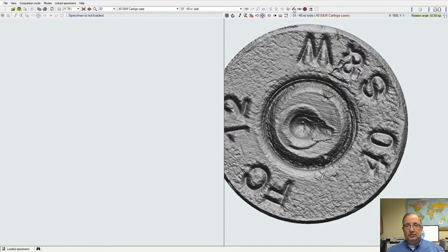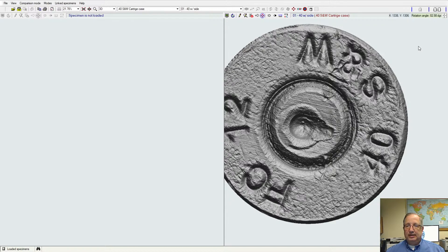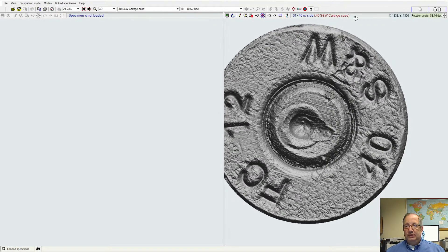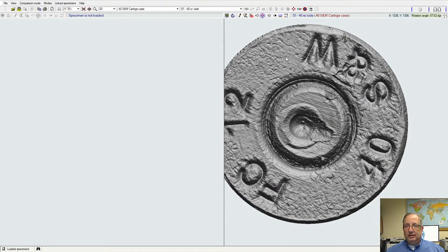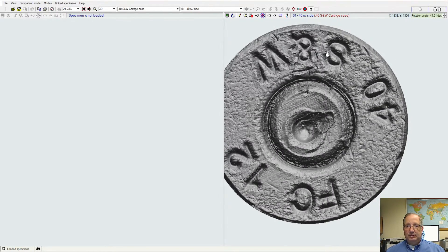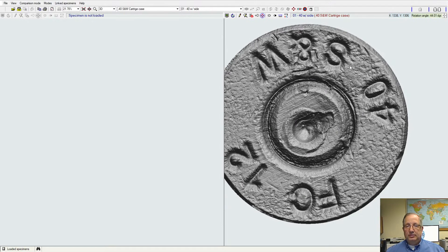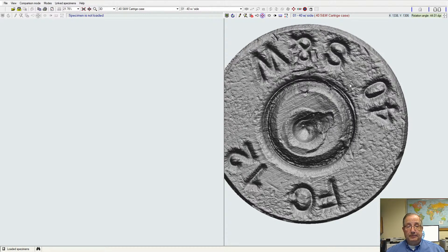Let me just sort of hide my lighting controls, and now what we're looking at is this small window on the top here is showing the side of the cartridge case, which is shown in this green rectangle on the side here. If I want to move that region of interest that I'm examining, I can reposition it in that window to be able to view the section that I'm interested in.